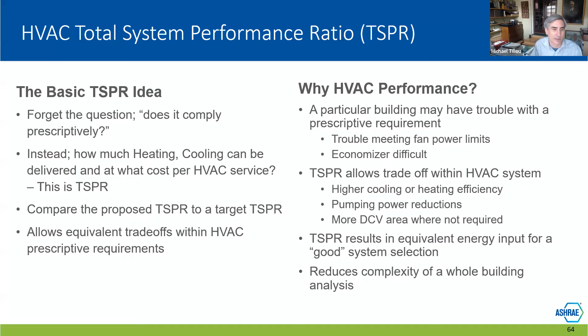So what is TSPR? The metric that we selected for TSPR is the ratio of your project's heating and cooling loads that are required to be delivered by the HVAC system divided by the annual HVAC operating input. And we say input for a very specific reason. The denominator of TSPR can be cost, it could be energy cost, it could be site energy, it could be source energy, it could be carbon emissions. The nice thing about TSPR is it does not have to be limited to just a cost analysis. A jurisdiction can adopt it and decide what metric makes sense for their jurisdiction to evaluate.